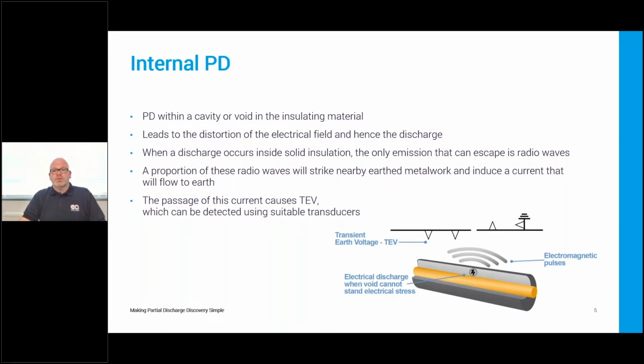So what is it? Well, when a discharge occurs inside solid insulation, it emits radio waves, and a small proportion of these radio waves will strike nearby earth metalwork, which will induce a current, and that then flows to earth. It's the passage of this current which causes TEV, or transient earth voltage, and that can be detected using a suitable device. So when you hear someone from EA banging on about TEV, which we do tend to do quite often, this is what we're referring to. It's a sure sign that PD activity is present.